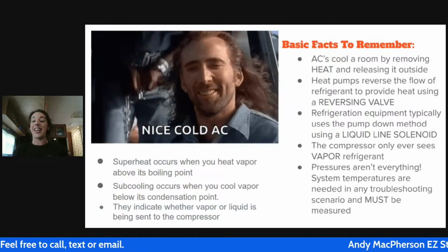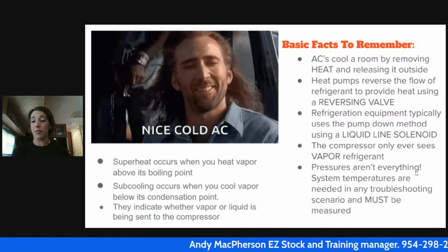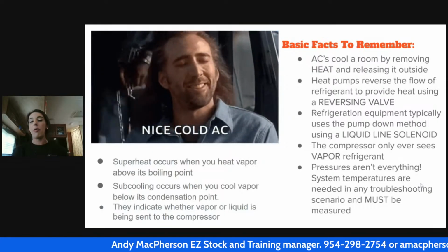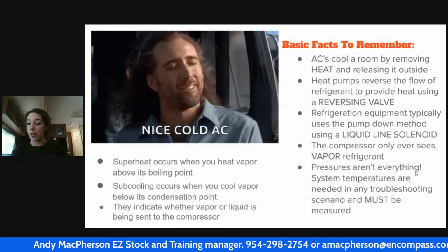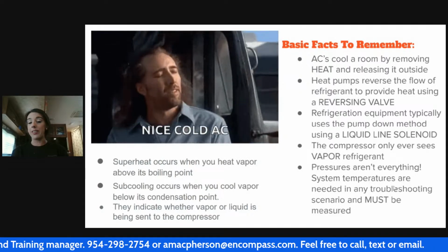Now we know better. Now we can't be having that, because even if you just had an excess of refrigerant, that could make that line cold, right? We have to be very, very careful that we're testing and we're not just guessing. And again, pressures aren't everything.